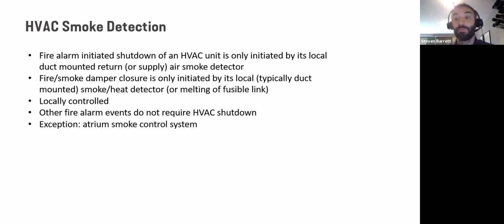So think about the local control. It's only the device itself that's going to be shutting down. Other events are not going to trigger an HVAC shutdown. Some projects may choose to do that. And again, back to the static and dynamic dampers idea. If you were to specify static dampers, they would only work if you did shut down the unit when you detected smoke. So in that case, again, you don't have to shut down the unit per code requirements if the smoke damper's detector goes off. But if you specified a static smoke damper, then it wouldn't close unless you did shut down the unit. So hopefully that made sense.